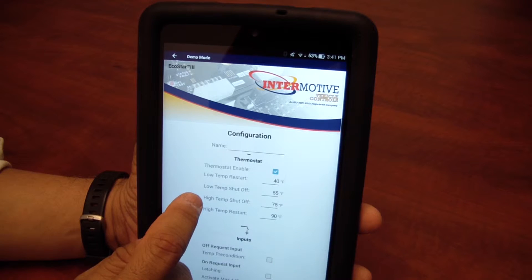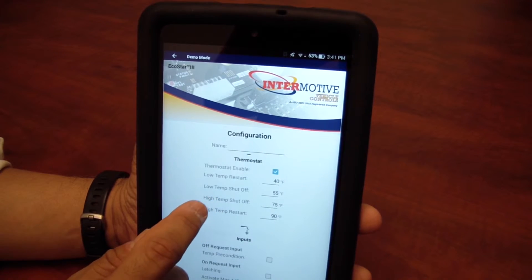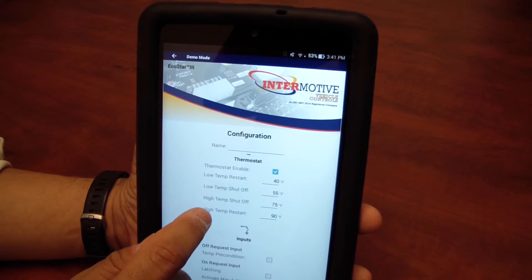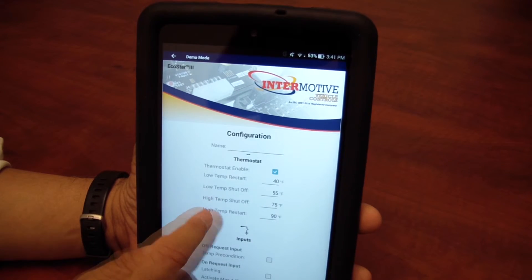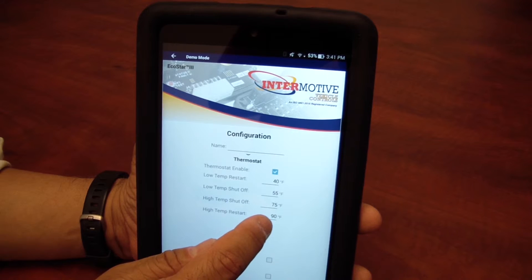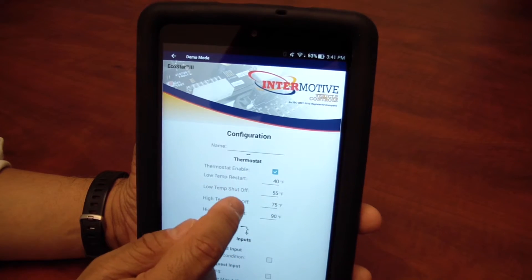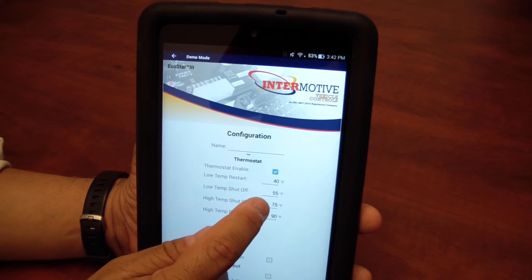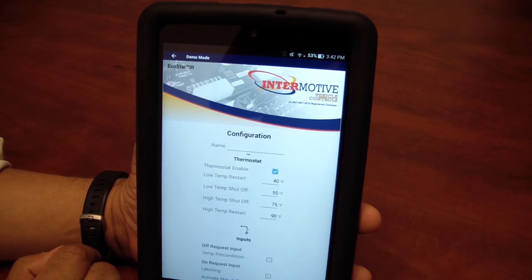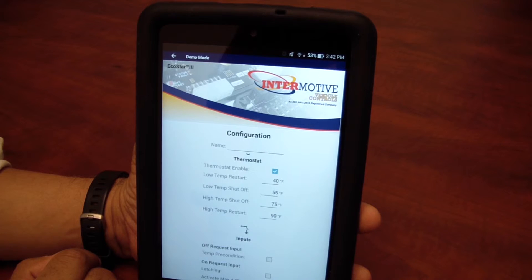On the high side, if the temperature gets warmer than 90 degrees, restart the engine, cool it down to 75 degrees, then shut off again.